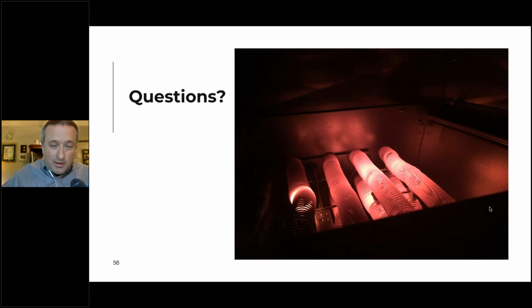It may or may not actually have the strips in there, and traditional air conditioning systems don't have it. Although you may get what's called an electric furnace, which would be an air conditioner with resistance backup, or resistance actually as the heat, which to me is asinine. You can have it cost two-thirds less by just putting in a heat pump version, which costs like $300 or $500 more wholesale. It's crazy not to do that, but out west where you've got 7-cent kilowatt hours, that's when you'd do it.